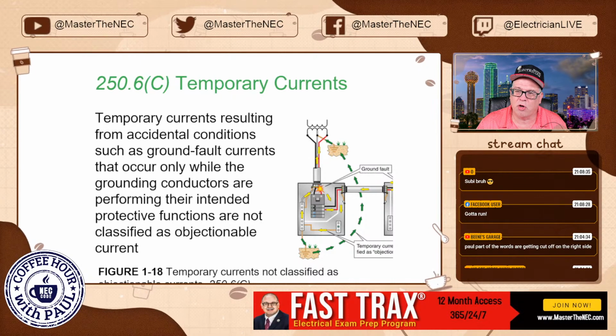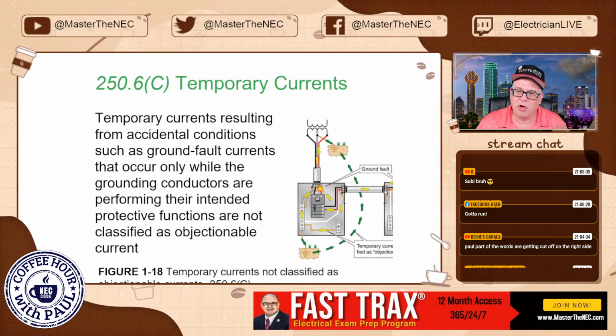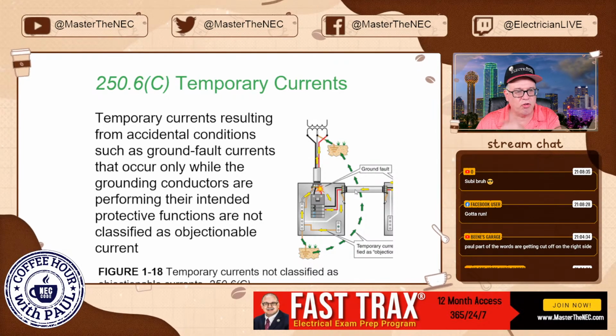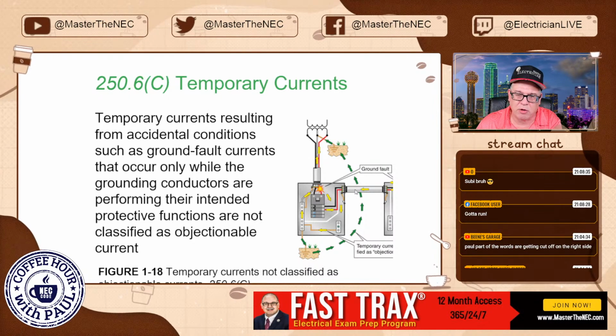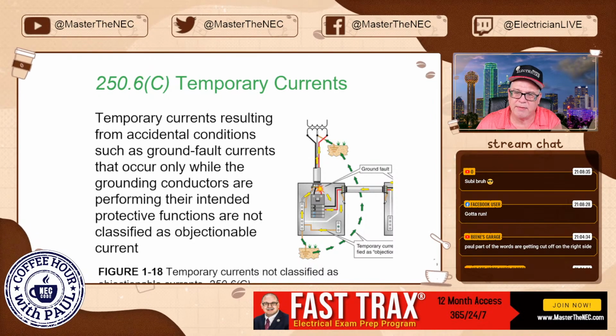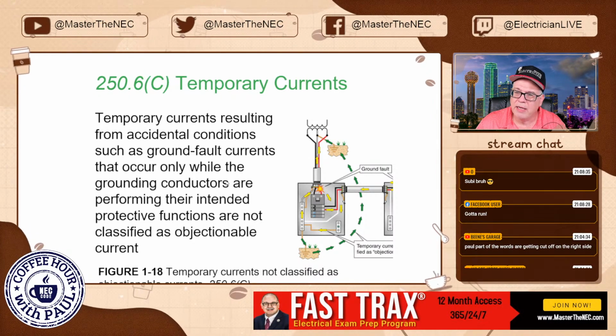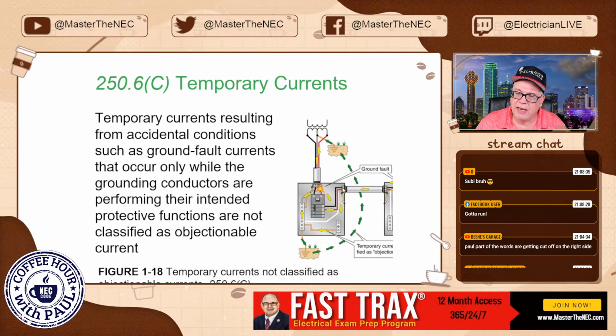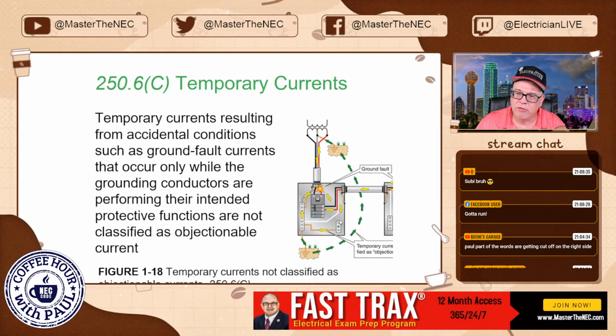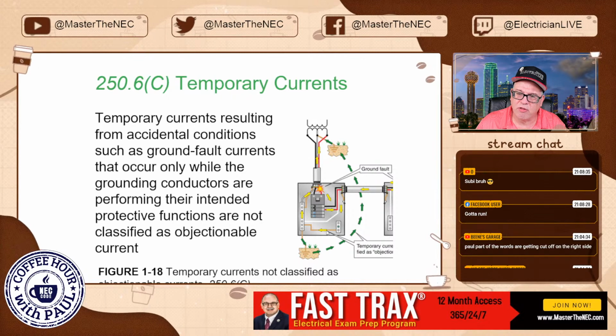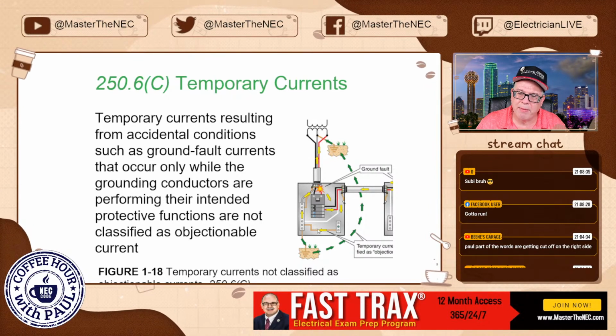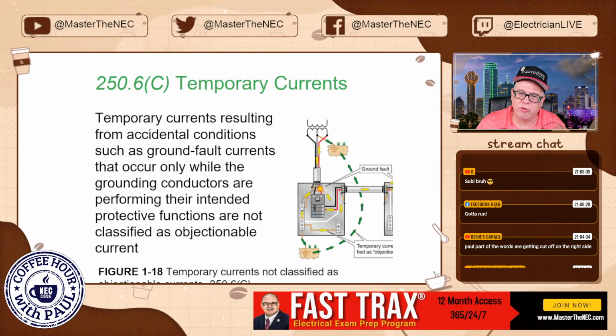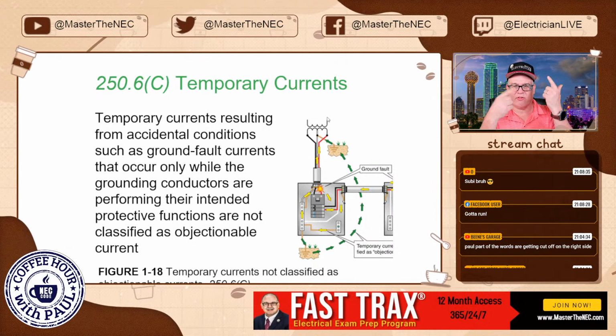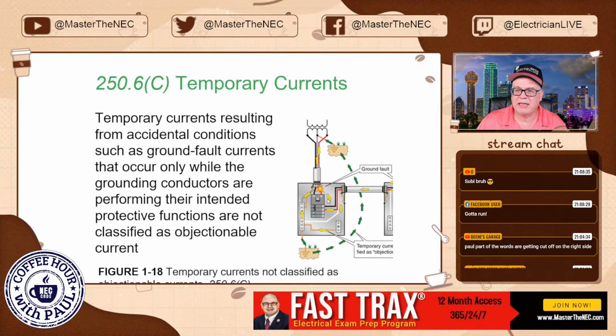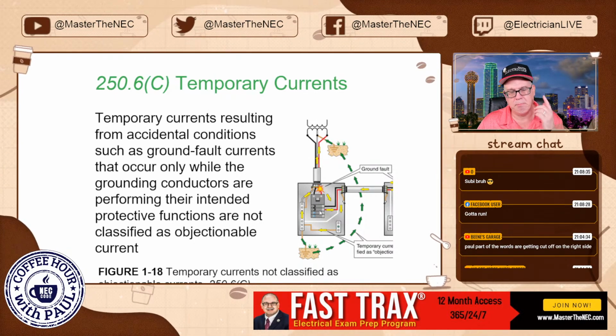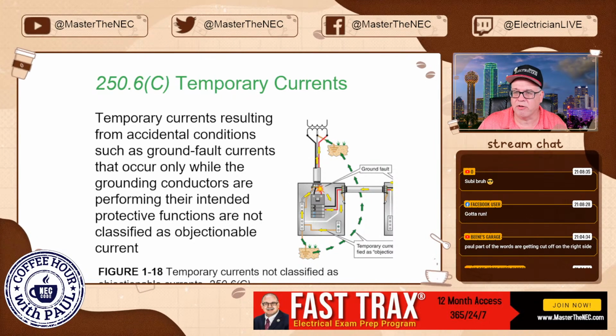We have a fault to the enclosure right here. It gets back on the enclosure, comes through the raceway. We'll assume this is rigid and it is allowed to be an equipment grounding conductor per 250.118, no wire run. It comes back here and it's going back through the enclosure and it gets over here on the main bonding jumper over to the ground and neutral conductor, goes to the source, completes the circuit, and guess what? Clears the overcurrent protective device. Boom, bada bing, bada bang, everything clears, okay?